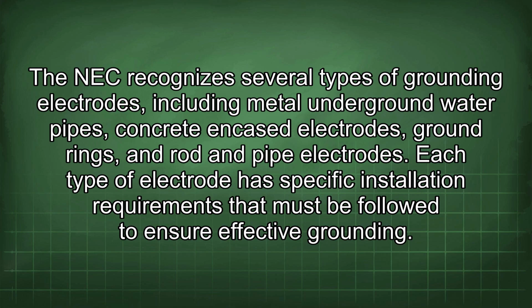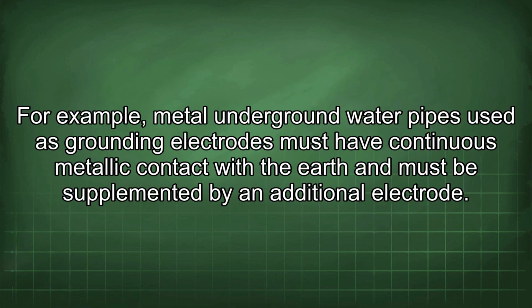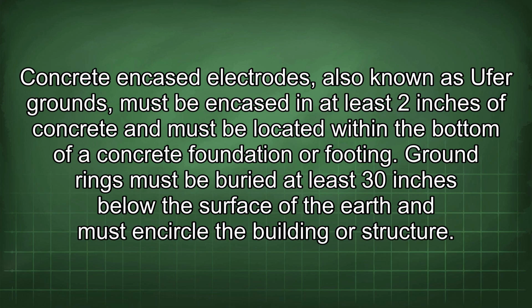Each type of electrode has specific installation requirements that must be followed to ensure effective grounding. For example, metal underground water pipes used as grounding electrodes must have continuous metallic contact with the earth and must be supplemented by an additional electrode. Concrete encased electrodes, also known as UFER grounds, must be encased in at least 2 inches of concrete and must be located within the bottom of a concrete foundation or footing.